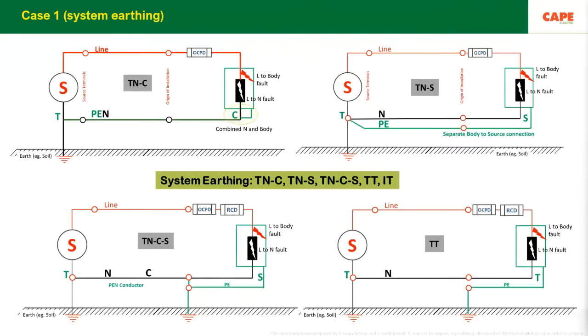Actually, on fundamental safety, as already told, up to 11 kV supply, 46% or 43% of accidents and deaths are happening at the 11 kV, and probably a large amount in the low voltage electrical distribution. Here, the electricity supply company has a lot of responsibilities. The safety regulations of the government of India say you should follow a TNS system, meaning a 5-wire system, or an earthed neutral system, TNCS, 4-wire system.